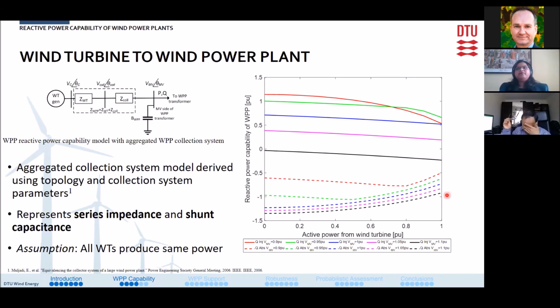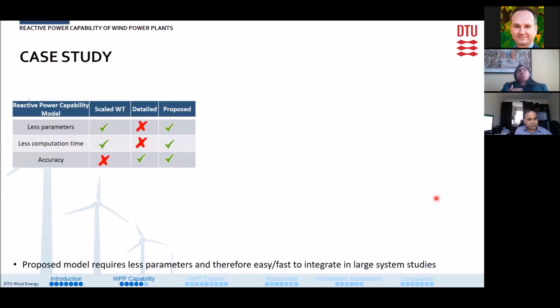So here is the active power and voltage dependent reactive power capability for the wind power plant. It is similar to the one seen before for the wind turbine, only that it is a bit reduced because of the losses in the collection system. Now, if we use a detailed wind power plant model in order to calculate the reactive power capability, we will get the most accurate capability curves. However, the detailed model requires lots of parameters, and inclusion of hundreds of detailed wind power plant models for large system studies may not be feasible.